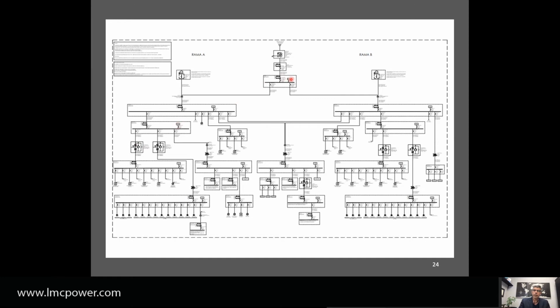Remember, we have category C, category B, and a branch panel category B - different cascading levels of protection. It's not so much the cost of the UPS; the category B surge protector will cost you under $1,000, but it's protecting, let's put a number on it, $200,000 worth of UPSs. What they're really protecting is the continuity of operation of the rest of their system. They make money on the operations of the system, so they could lose millions when they could lose just hundreds of thousands in equipment by providing a $1,000 piece of surge protection.